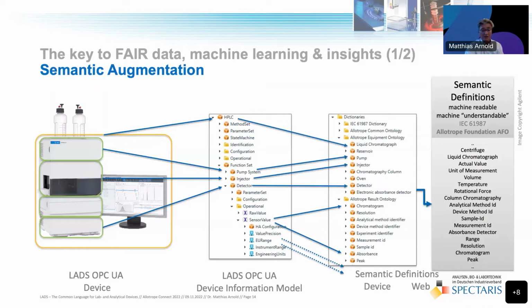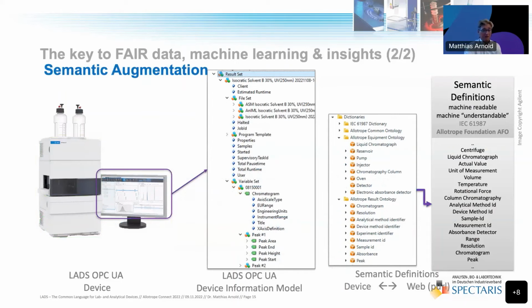This not only works for a detector, which is a sensor value, but you understand this is not just some sensor value, it's the detector of an HPLC providing absorbance measurements. It also works for the result data, because the result data is also represented in the information model of LADS OPC UA, for example in forms of files like an ASM file, so Allotrope Simple Model, or an ADF file or an animal file.